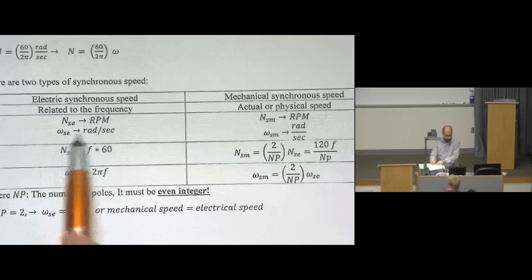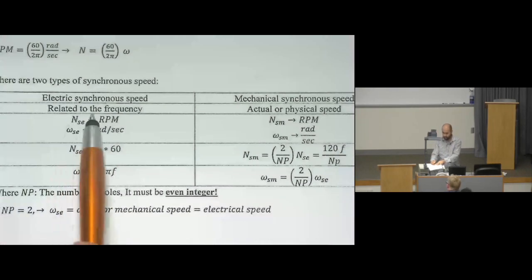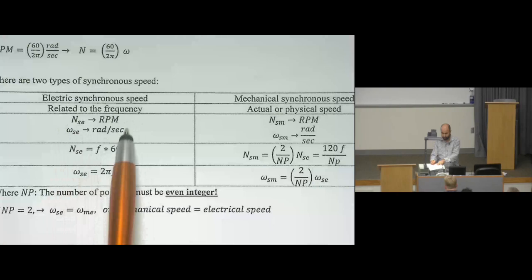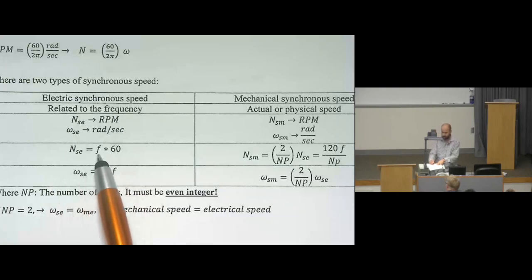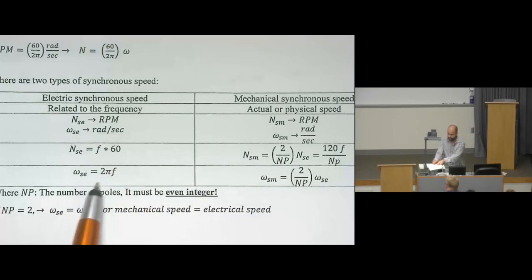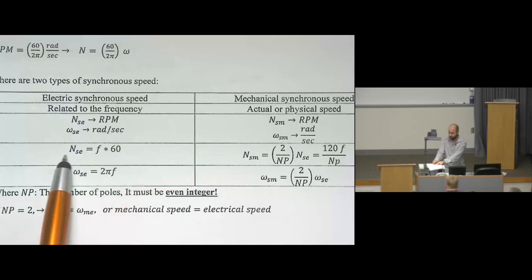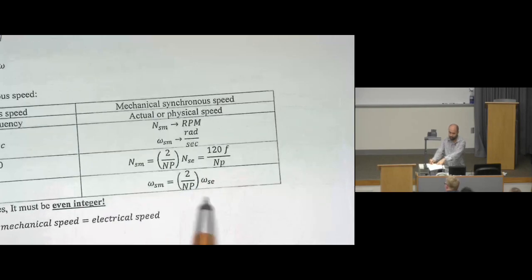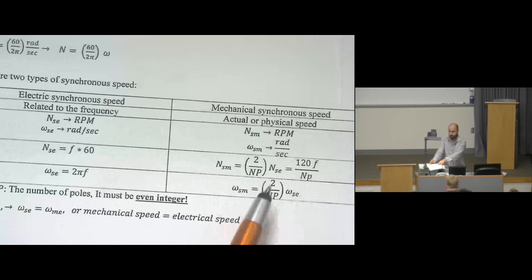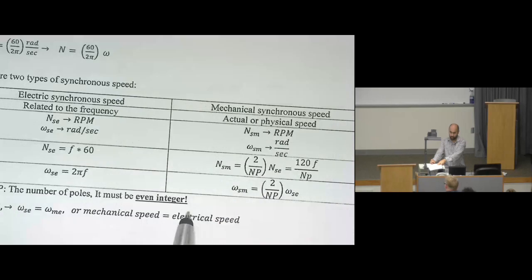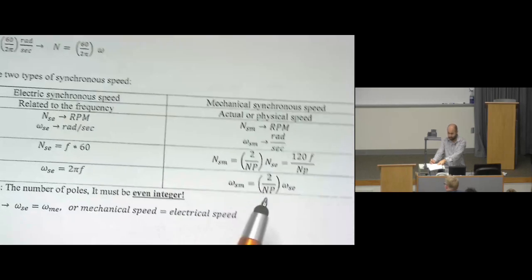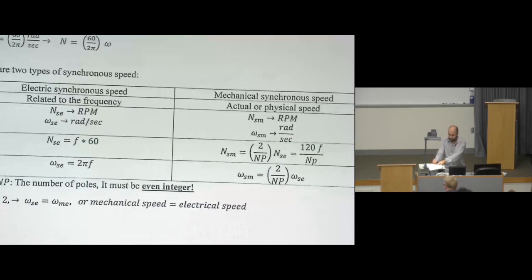Electrical speed is associated with the frequency: RPM equals F times 60, omega equals 2 pi times F. This is for electrical. For mechanical, just add 2 over the number of poles, and keep in mind the poles must be an even integer. The only case where electrical speed and mechanical speed are the same is when the number of poles equals 2.